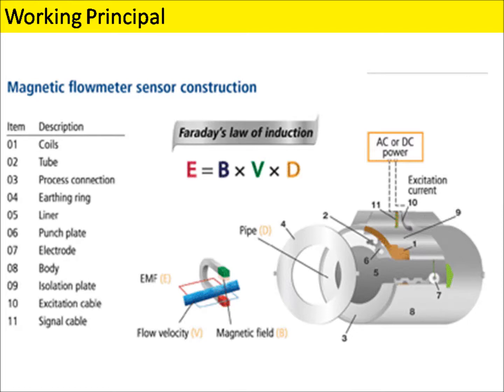The liquid flow, magnetic field, and line between the electrodes form the X, Y, and Z axes. Figure 1 goes into more detail about the actual construction. Magmeter users appreciate how the interior surface of the device can match the upstream and downstream pipe diameter, and how there are no obstructions in the flow stream. The flow meter itself must have an insulating lining, which can be made from rubber, Teflon, ceramic, or other materials capable of standing up to erosive or corrosive media.